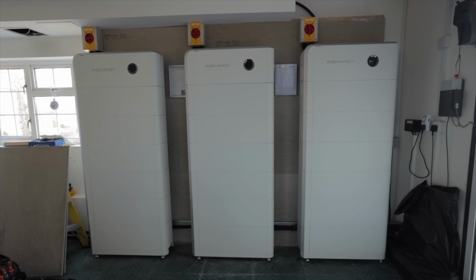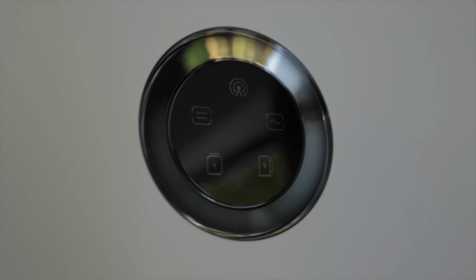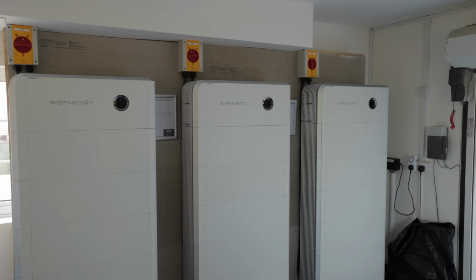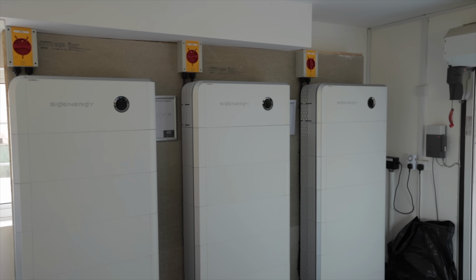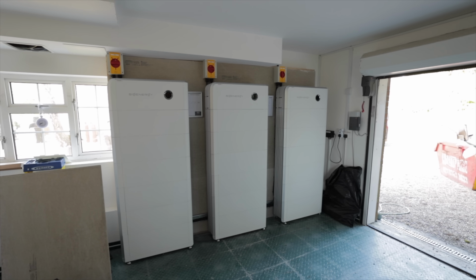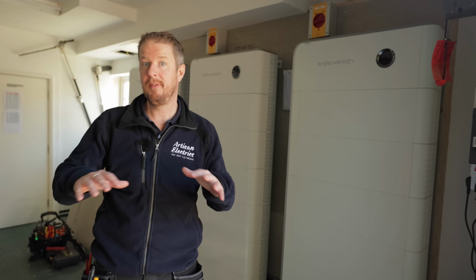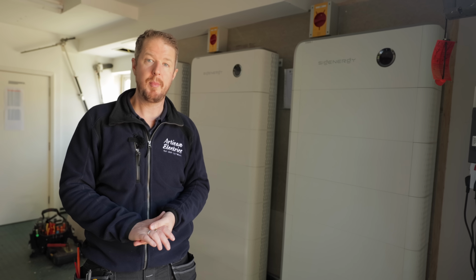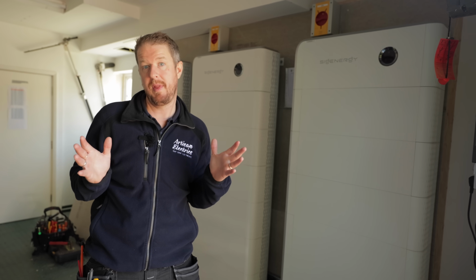Because what we want to be able to do is discharge the batteries to match their peak demand in the property as well. So for example, if we took these down to 10 kilowatt inverters, then the maximum charge and discharge rate of the entire system would be 30 kilowatt. That might not be enough to cover all of the loads within the property. It would mean that the batteries would charge up slower, but still probably within that window. So if we fitted 10 kilowatt inverters, 48 divided by 10 gives us 4.8 hours. In other words, it would just be within that 5-hour window.